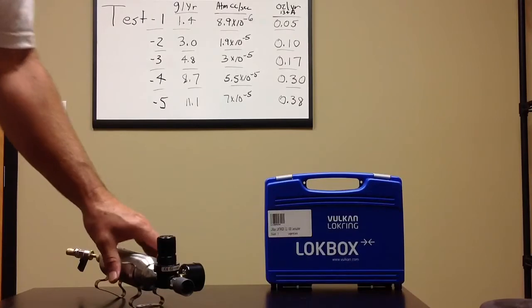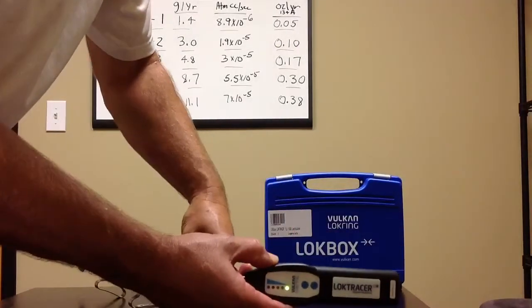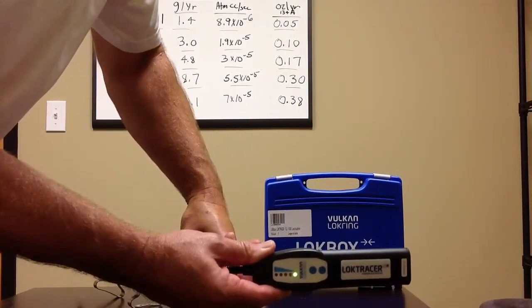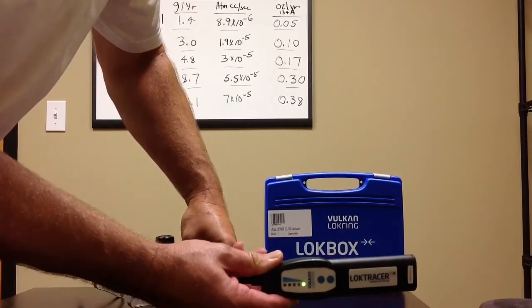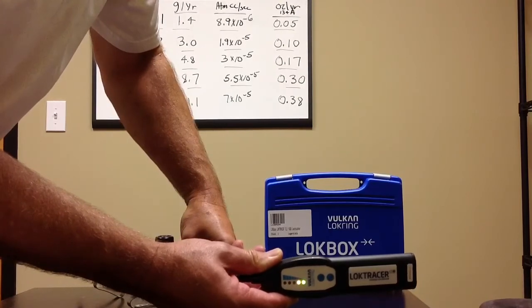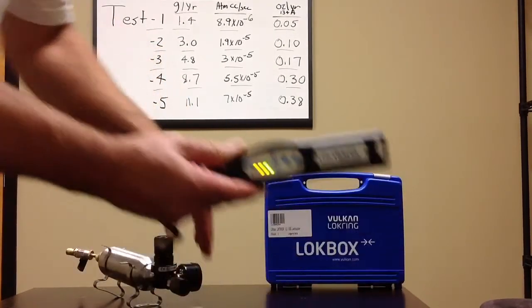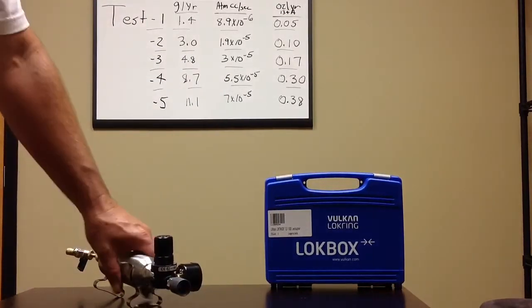Next setting will be for the 3.0 grams per year or one-tenth of an ounce of R134A. So we'll expose the leak. Okay. So it's a little bit stronger response there.